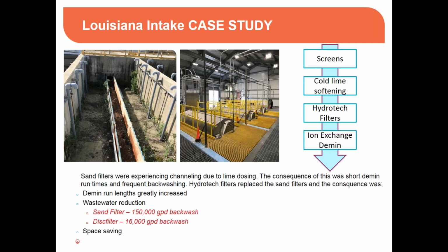This is an intake water system in Louisiana. They had real trouble with their sand filters due to channeling, because of a couple of reasons, but the hardness of their water was extremely high. So they replaced their 8 sand filters with 3 Hydrotech filters. So now the system is screens, and then lime softening, cold lime softening, and then the Hydrotech filters, and then it goes to the process. The client was happy with it. One of the main benefits, even besides the footprint, besides the CapEx, was the backwash water savings. Like the volume of water decreased almost by an order of magnitude. You can see the sand filters were about 150,000 gallons per day use of backwash, and the disc filters are about 16,000.